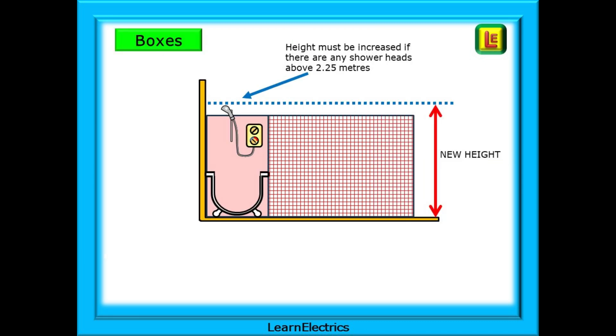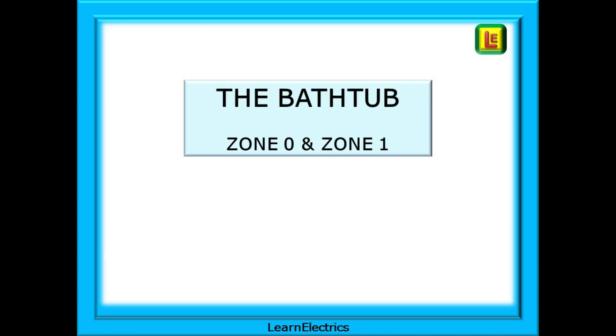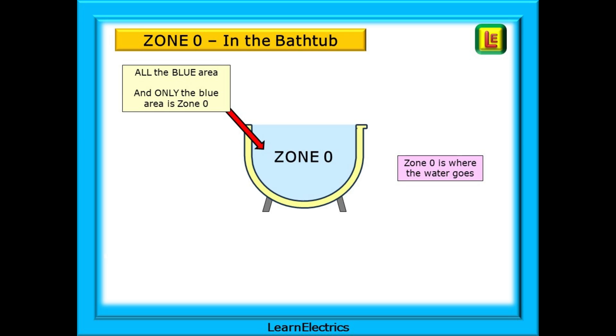The height requirement is 2.25 meters. However, if the shower head or other water outlet exceeds this height, then the height requirement increases with it. Zone 0 is the space inside the bathtub — all the blue area shown on this drawing and only the blue area. Think of zone 0 as where the water goes, right to the top of the bathtub.